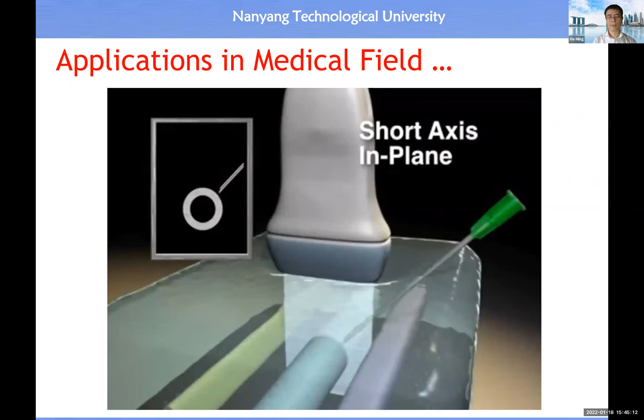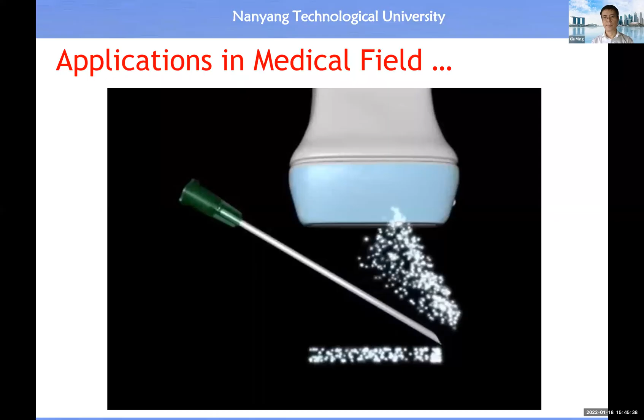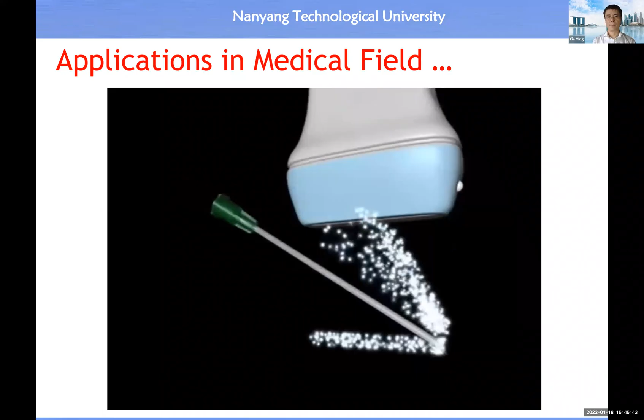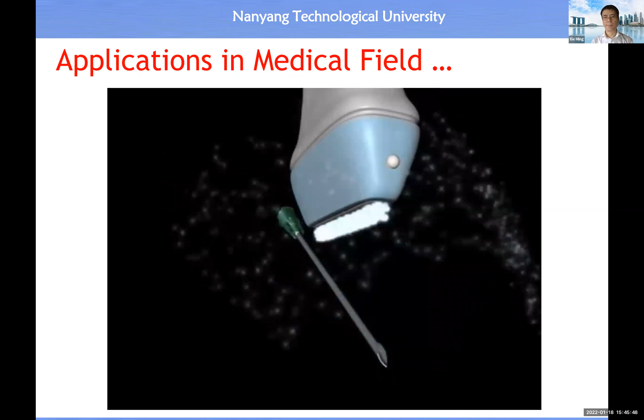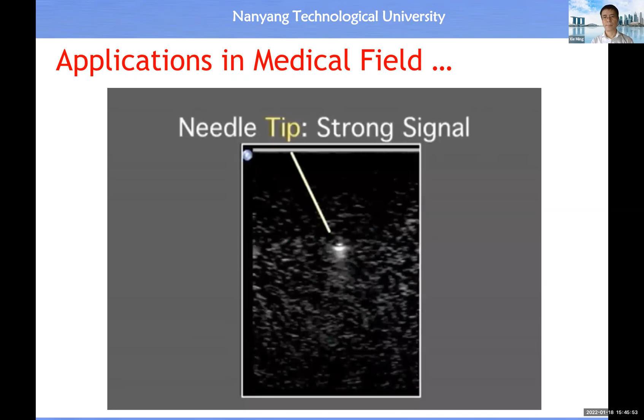Block needles are specular reflectors, meaning they reflect sound back to the receiver over a narrow angle. As the angle between the transducer and needle increases, less sound is reflected back to the receiver, and the signal becomes weaker. We can also see that this is true for sound reflected off the sides of the needle shaft. With the short axis out-of-plane approach, the needle will be seen best when the tip is within the plane of imaging. The shaft gives a signal that...